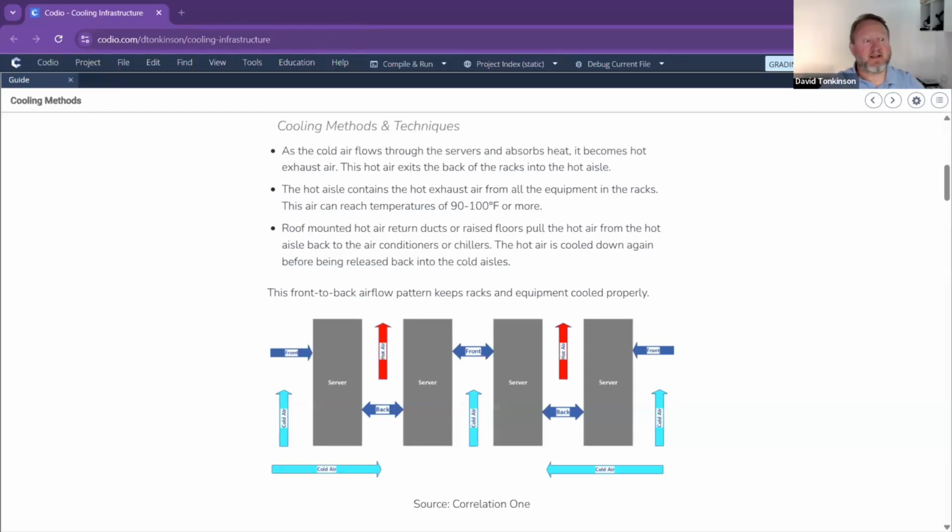Heat exhaust. The simple reason they tend to be placed at the front is because 99%, in fact, all manufacturers basically design their switches so they blow air from the front to the back. You can buy switches and other devices that are designed to be mounted at the back of a rack. Okay, and they suck air from the back and blow it out the front. But don't get them the wrong way around, because if you put them the wrong way around, you are messing up the airflow system. You don't want to be blowing hot air back into the systems you are trying to cool.